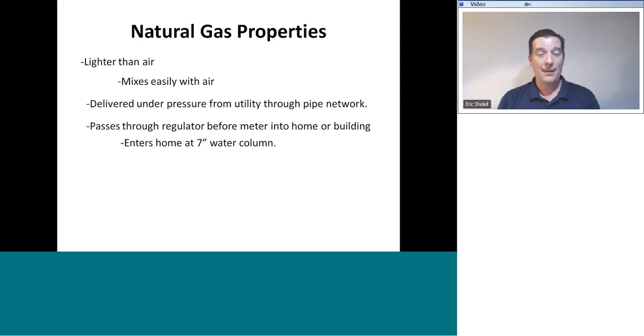1 PSI is equal to 28 inches of water column. So therefore, the pressure that natural gas enters a home after the regulator is around 7 inches water column, or 1/4 of a PSI. So the pressures that we're working with of natural gas are very low, especially inside the building.